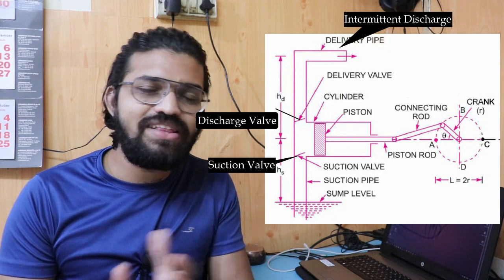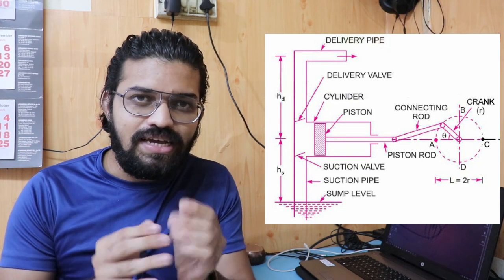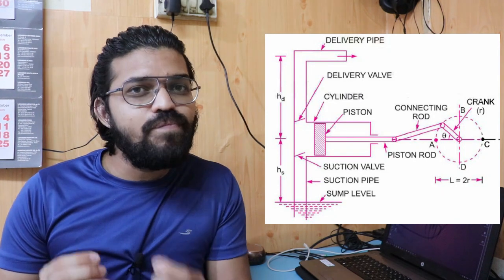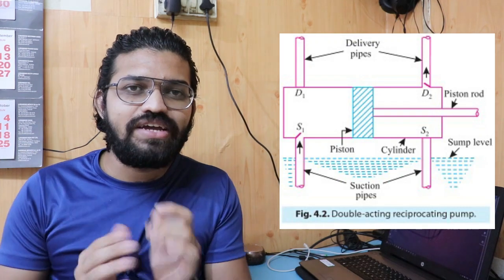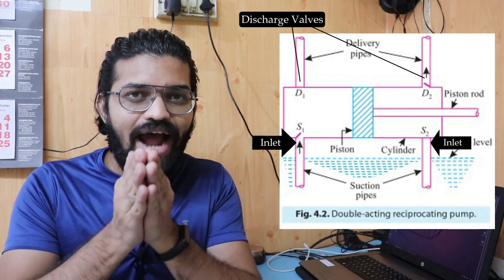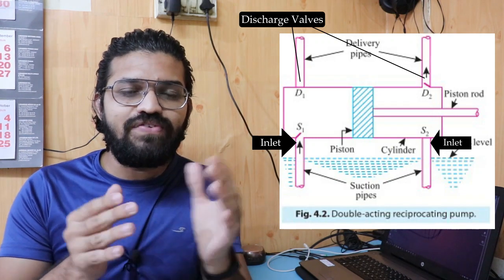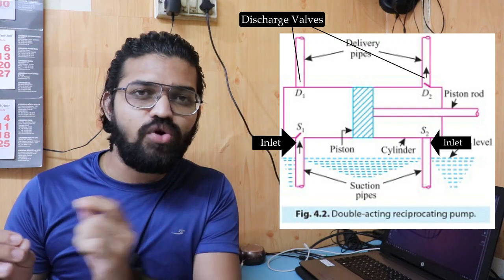To overcome the intermittent flow problem and improve the discharge, the cylinder-piston is slightly modified. Two inlet valves and two discharge valves are introduced in the double acting reciprocating pump. Here you can see the representation — two suction valves and two discharge valves are implemented, with the piston fitted at the center. The piston reciprocates between these two sides and the rotary motion of the crank is converted into reciprocating motion.